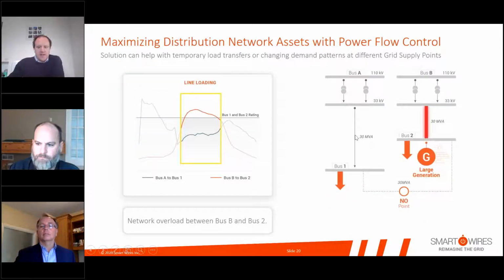On the flip side, you've got a lot of generation connected at bus B or bus 2, and at high solar output, high peak output times of the day, you're pushing a lot of power up towards the transmission system and overloading that circuit. Again, a solution that might be looked at would be to reconductor or build a new circuit between bus 2 and bus B.